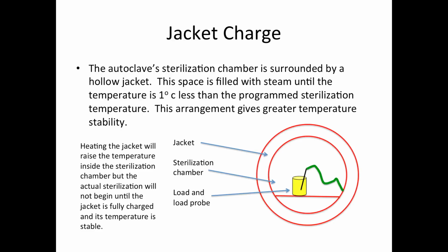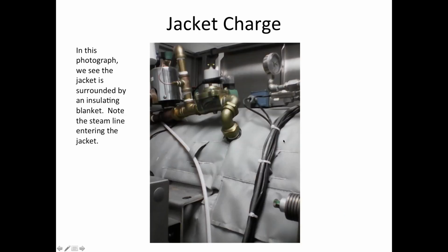We are emitting steam into the jacket. We are not emitting steam into the sterilization chamber. The actual sterilization does not begin until after the jacket is fully charged and its temperature is stable. So here is a picture of the actual autoclave behind those stainless steel panels. You'll notice that there's a steam line entering the jacket, which is surrounded by an insulating blanket.